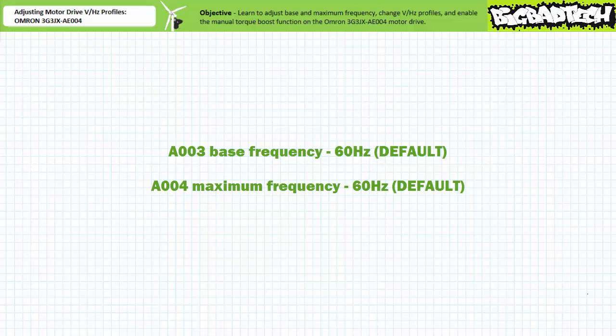Extended function parameter A004, maximum frequency, is user adjustable from 30 to 400 hertz. The default maximum frequency is 60 hertz. Let's keep the base frequency at the default setting of 60 hertz and change the maximum frequency to 100 hertz.